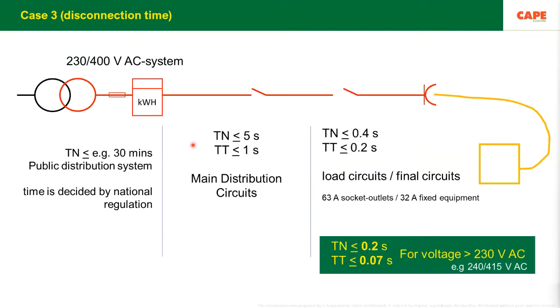Means all the metallic. I have a slide which I will explain later on. So these timings are applicable if you have implemented protective equipotential bonding. If you have not implemented protective equipotential bonding, then the disconnection times, I would say, have to be even lesser. So the third point is disconnection time of a circuit during a fault.